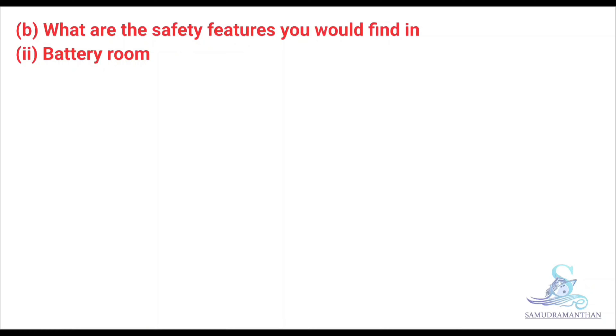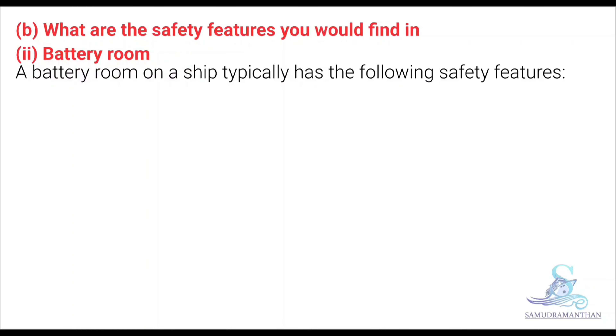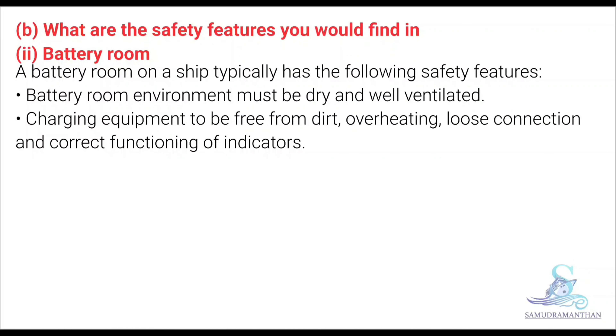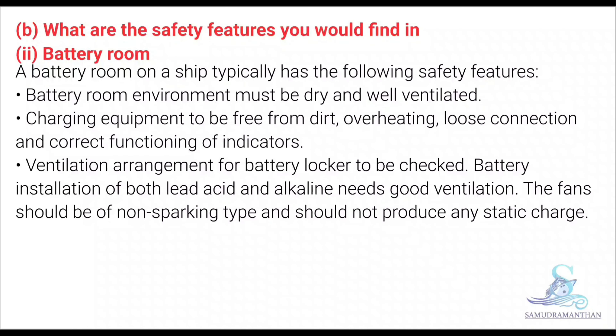Now we will discuss the safety features in the battery room. A battery room on a ship typically has the following safety features: the battery room environment must be dry and well ventilated; charging equipment must be free from dirt, overheating, loose connections, and indicators must function correctly; ventilation arrangement for battery lockers must be checked; battery installation for both lead acid and alkaline batteries requires good ventilation. The fans should be of the non-sparking type and should not produce any static charge.